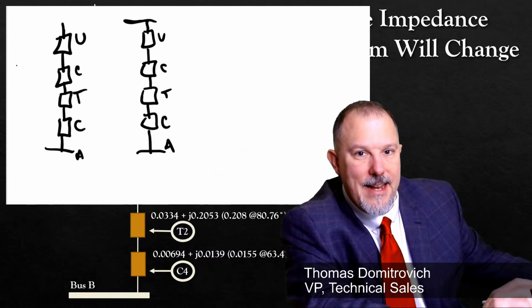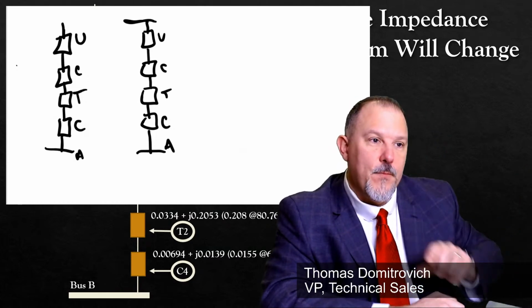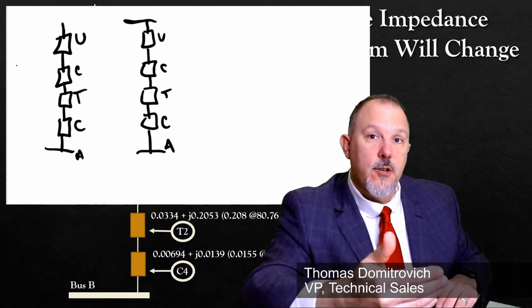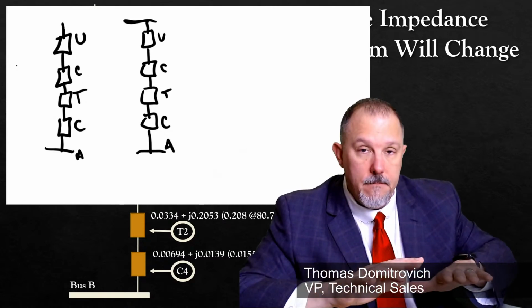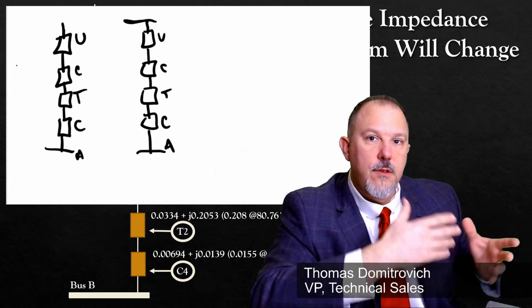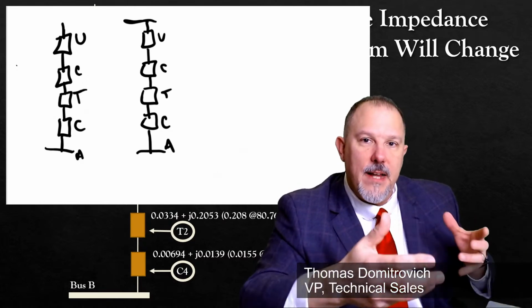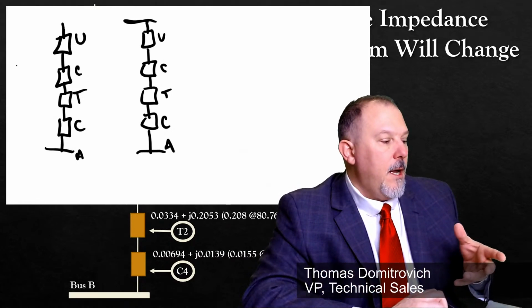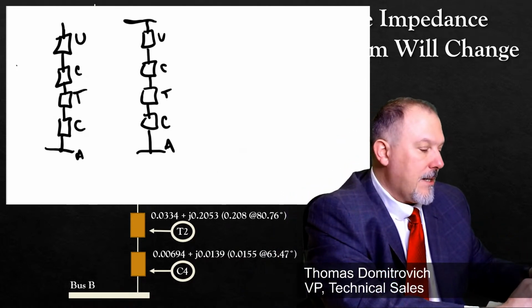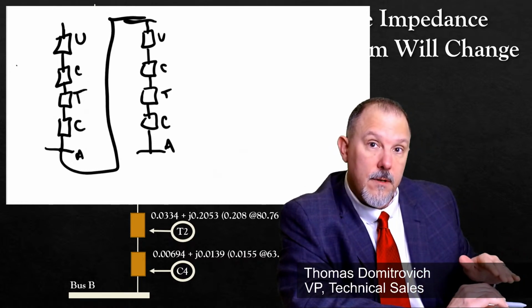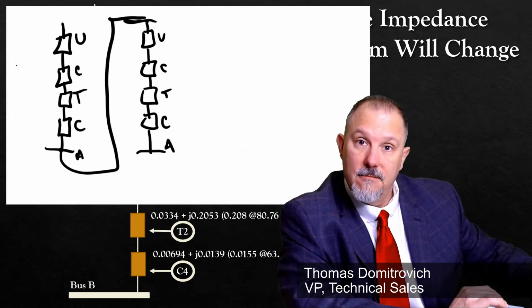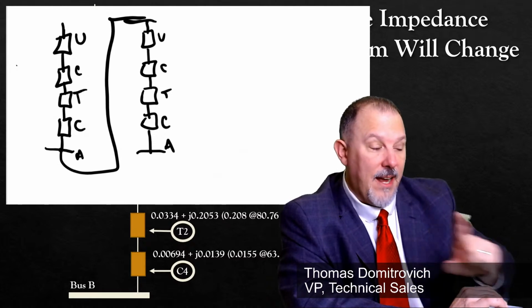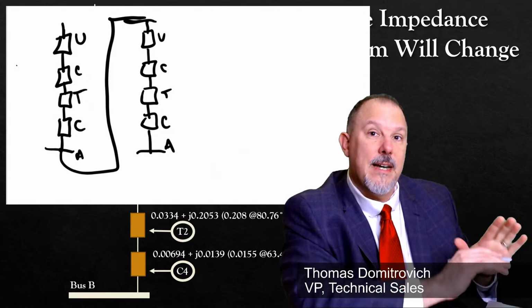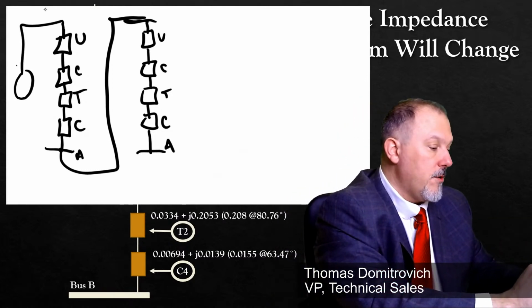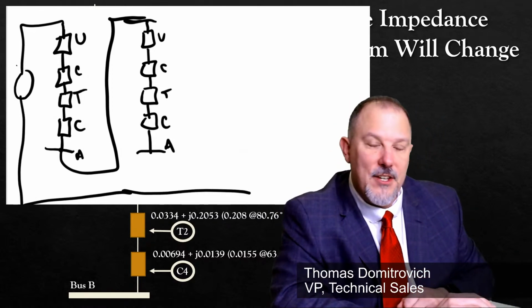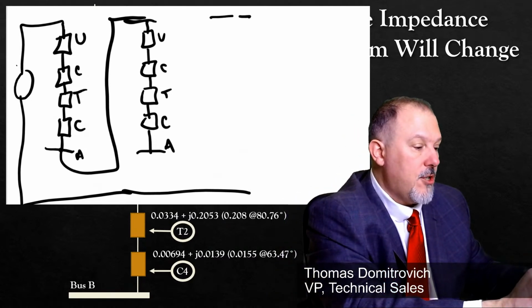The zero sequence. Now, here's what we do. Remember, each sequence, positive, negative, and zero, operates independently. They don't influence each other in any way. We break all of our components down into the positive, negative, and zero sequence. Because they don't impact each other in any way, when I draw my circuit, I need to basically connect these in series with each other. So I'm doubling the impedance so far. I haven't put zero sequence in here, but I'm doubling the impedance of my circuit. You think about it. There's my voltage source, and the other end of this circuit is going to be completed by the zero sequence circuit, which I'm going to draw here.